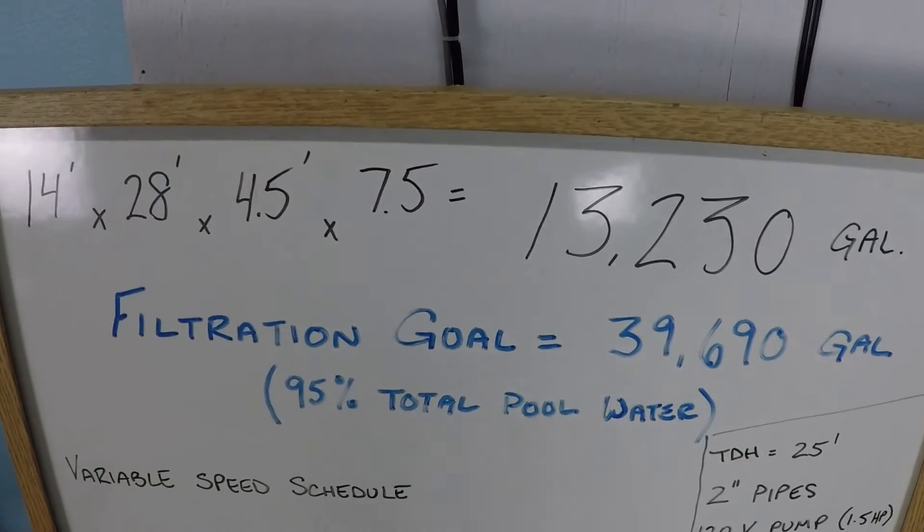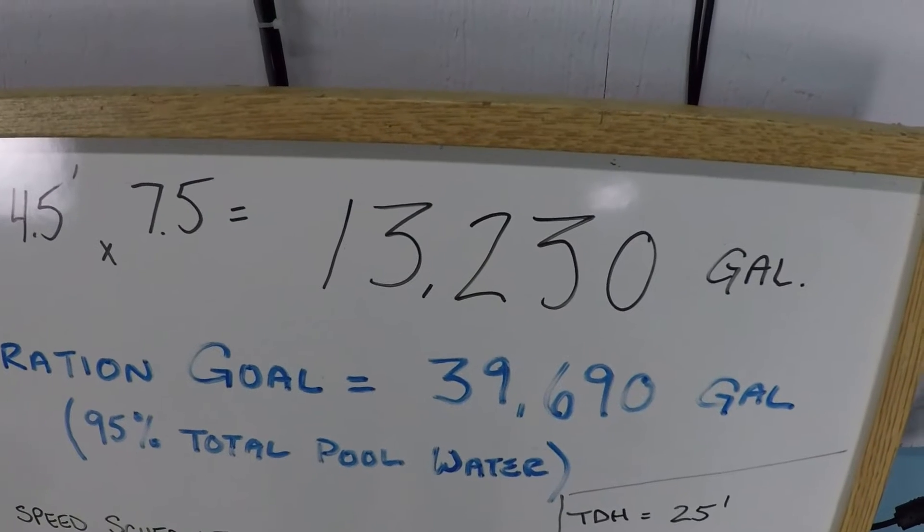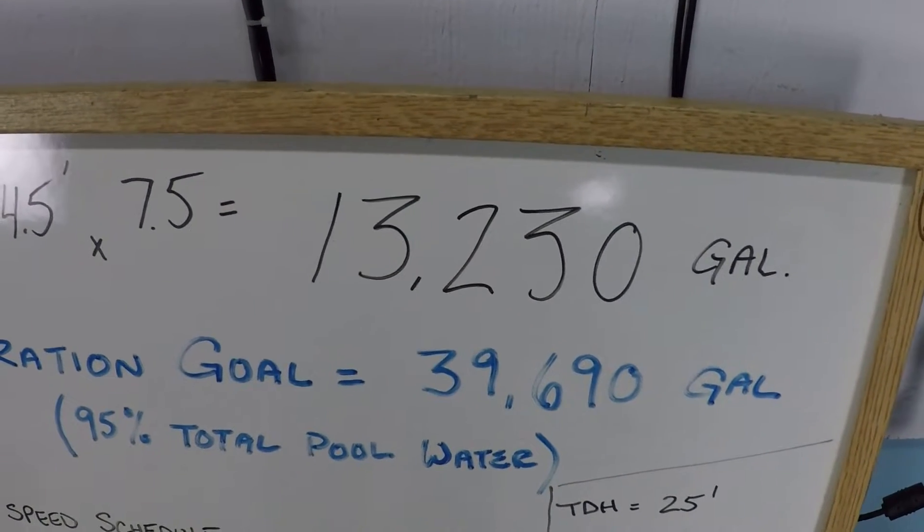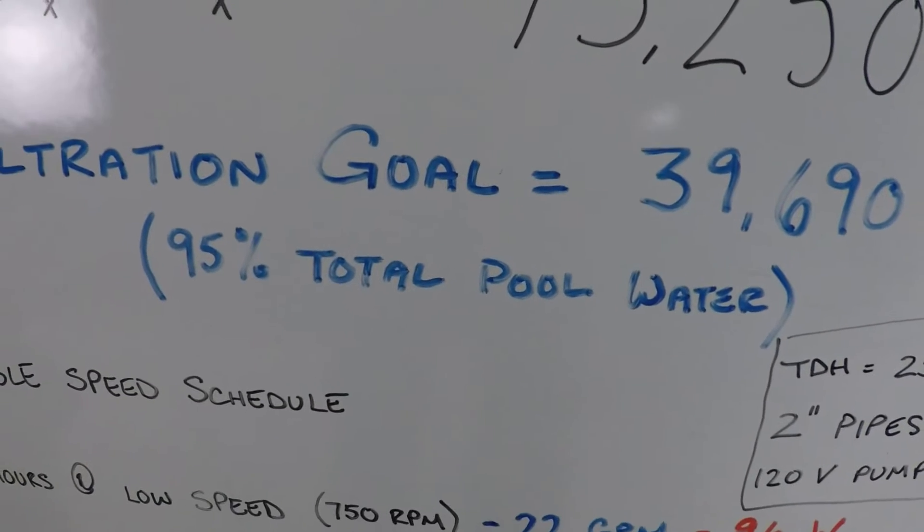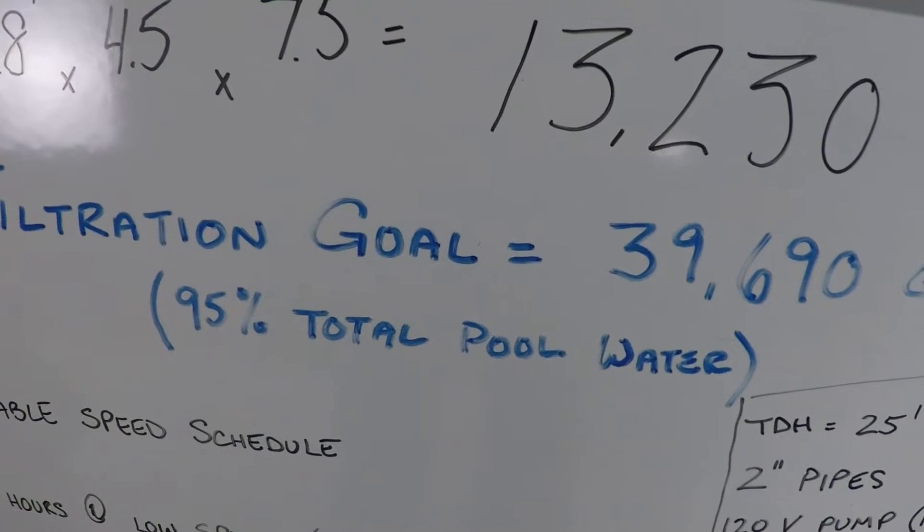So that means our filtration goal for this pool is 39,690 gallons, which is to say three times the volume of the swimming pool, because that's the point at which we have achieved 95% of all of the water in the pool being filtered at least one time.